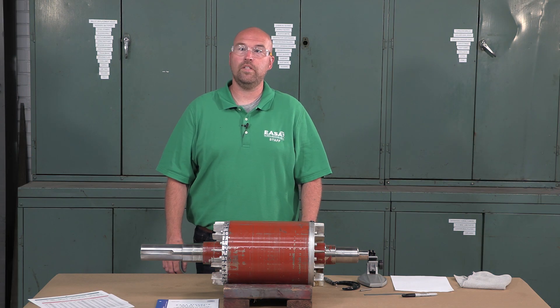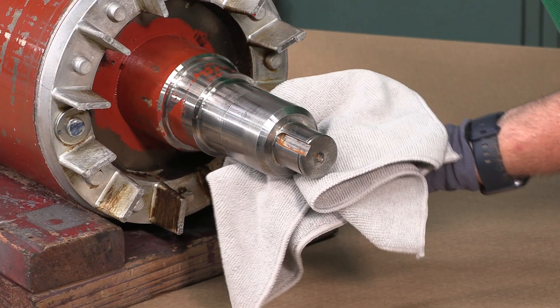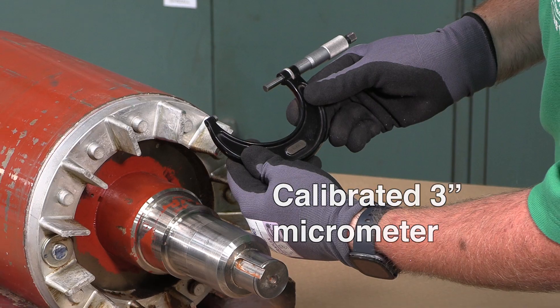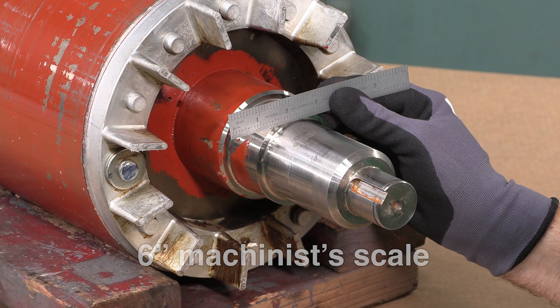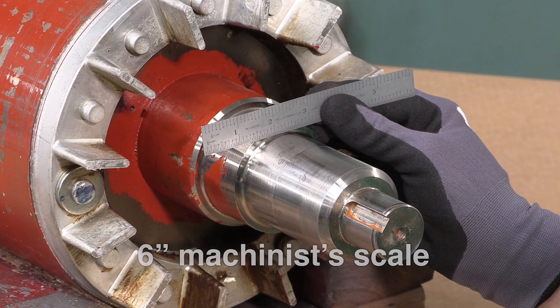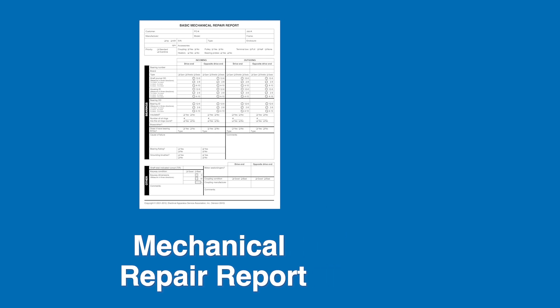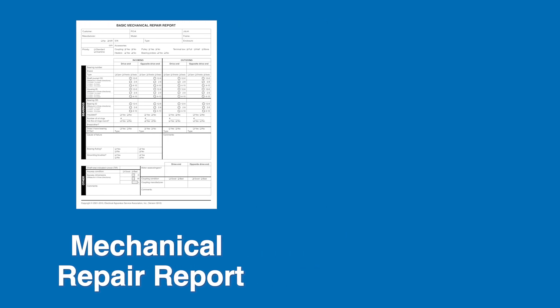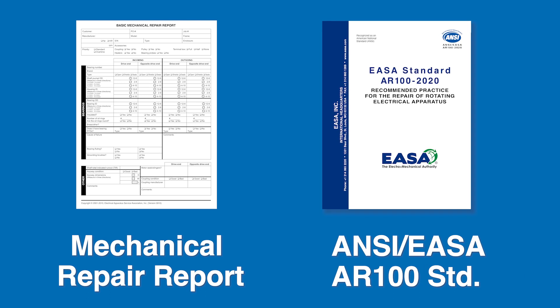To measure a bearing journal, you'll need a few tools and supplies: a lint-free cloth, a calibrated three inch micrometer, a micrometer stand for that three inch micrometer, a six inch machinist scale, and a permanent marker. You will also need EASA's mechanical repair report or other data card your service center uses, and the ANSI/EASA AR100 standard for radial ball and roller bearing shaft diameter tolerances.